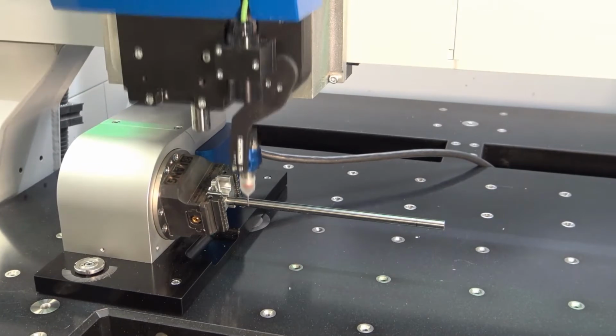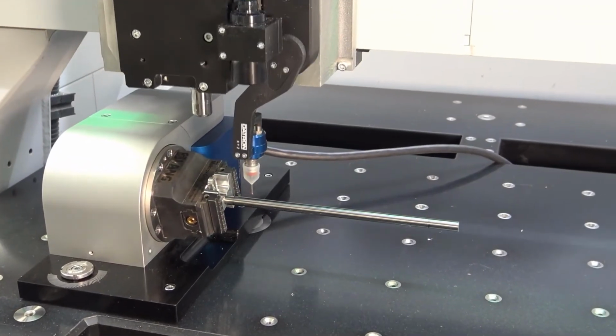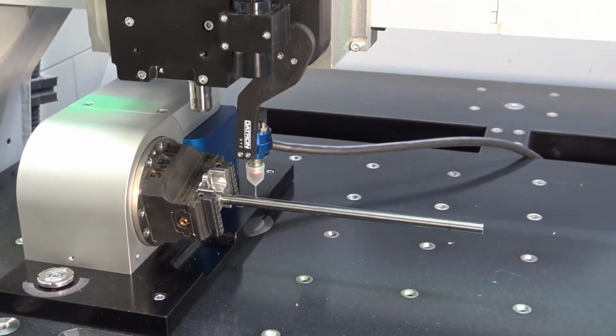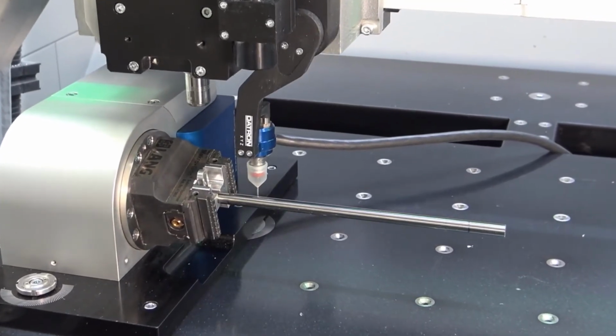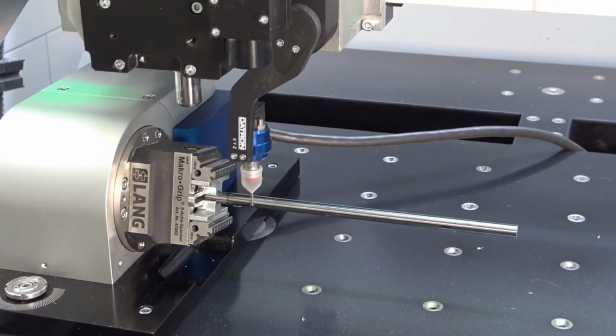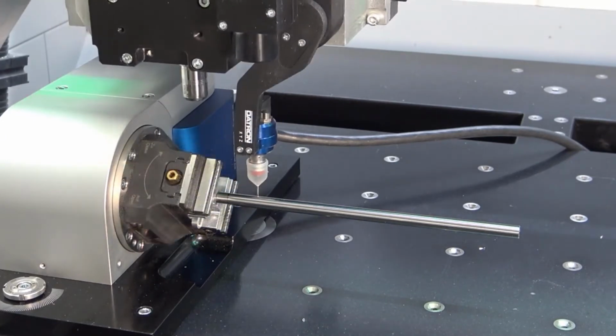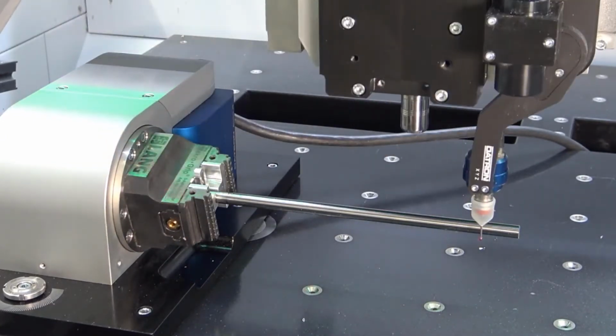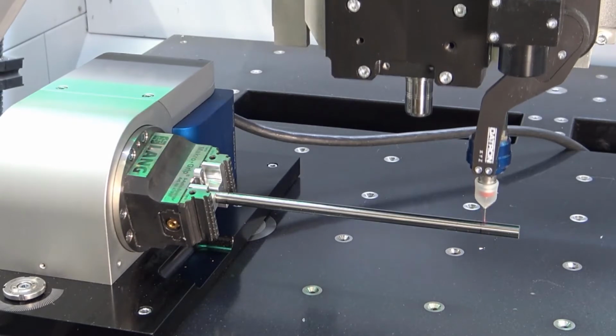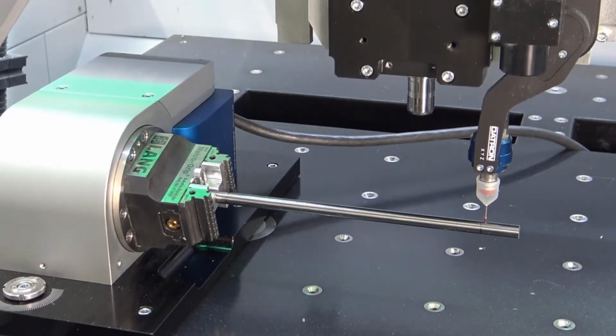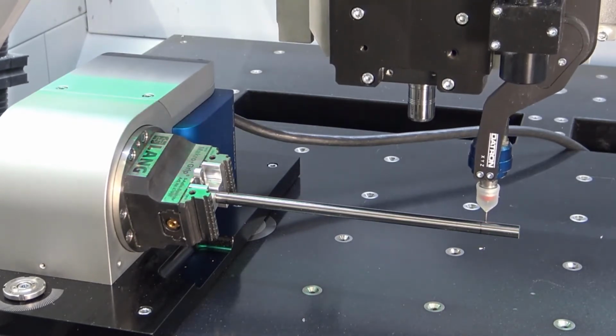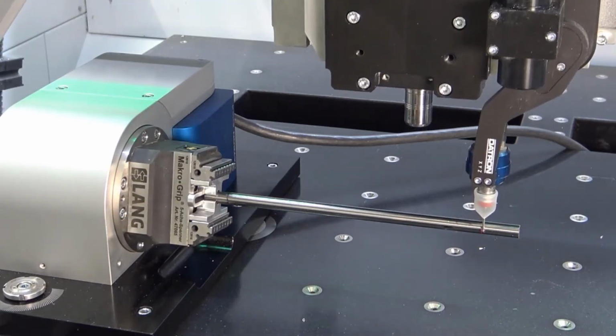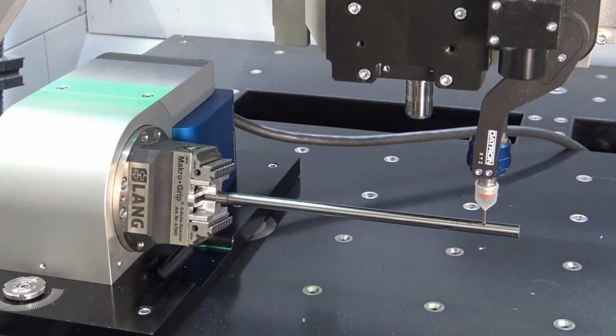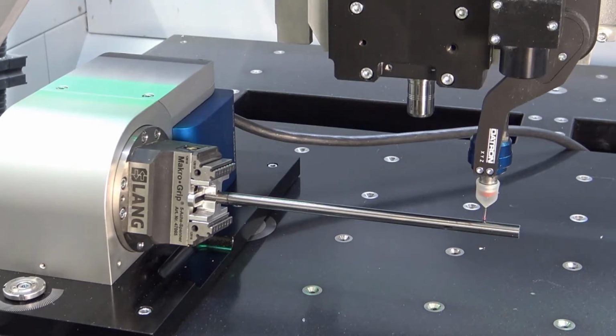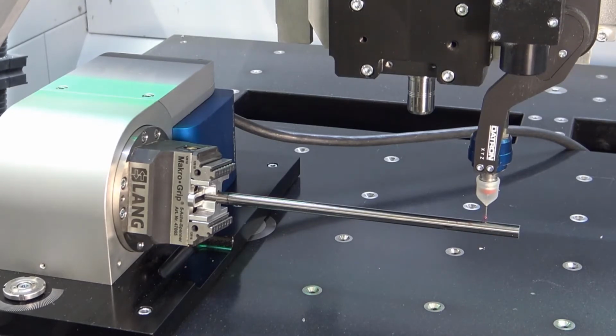So this is where we see the probe coming down and touching this round bar from different angles and on different positions. And with these values, the machine is able to compensate everything, to realign the angular deviation, and so on, so that you can be sure that the axis is locating your parts correctly afterwards.